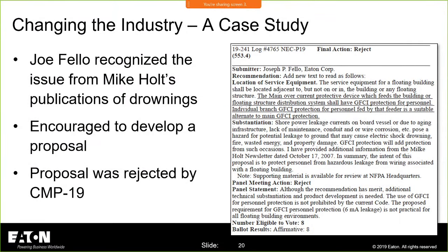I believe it was panel 19 at the time, because this was back a few cycles ago. This is what we submitted: we wanted the main overcurrent protective device, which feeds the building or floating structure distribution system, to have GFCI protection for personnel. We had an allowance that individual GFCI protection for personnel fed by that feeder is a suitable alternative to putting it in the main.